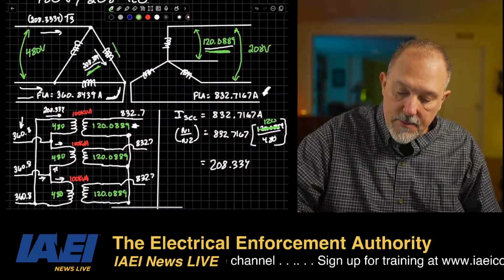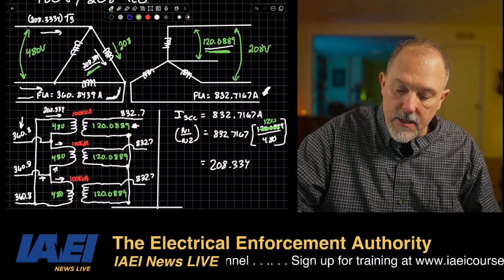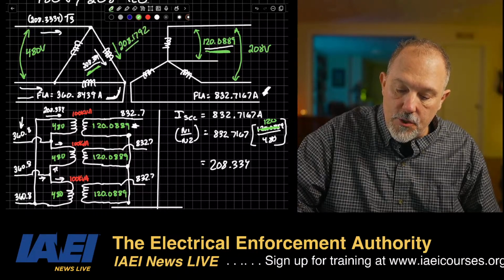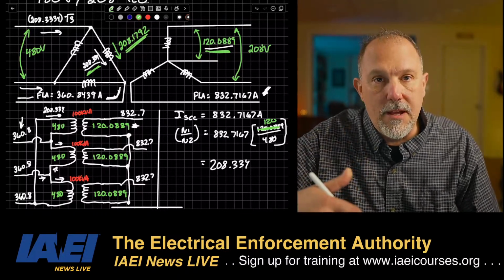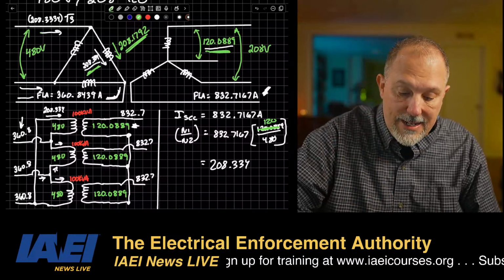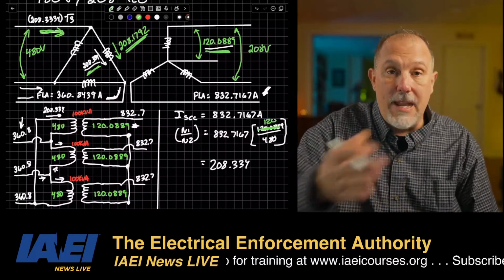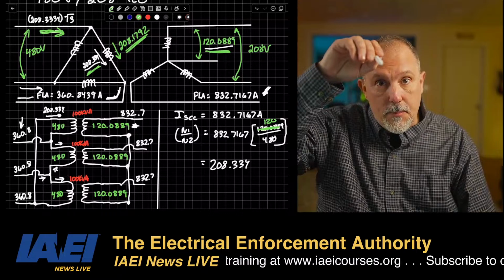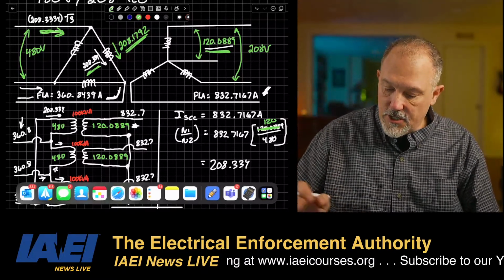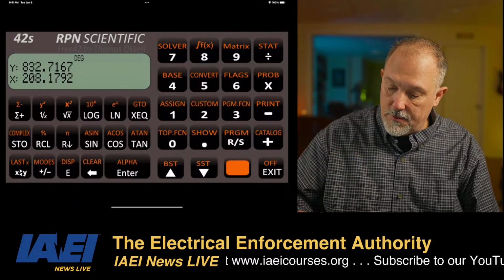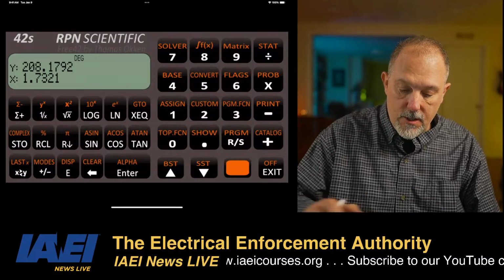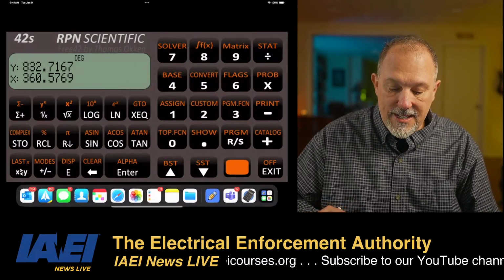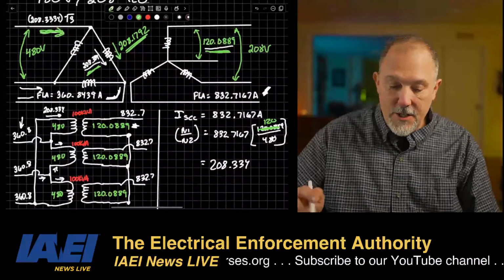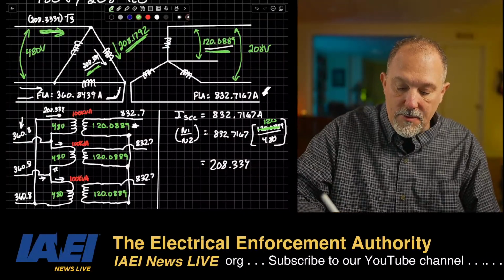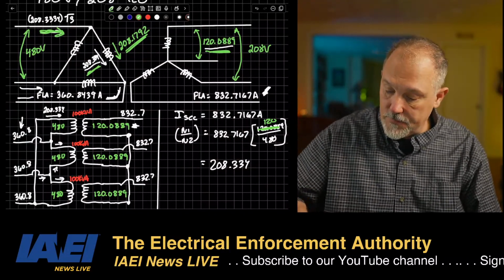So this number here becomes 208.1792. And then I have to multiply that by what? The square root of 3 to get the current on the line side, because that's just what's through the primary in a delta connected. So I've got to multiply that by the square root of 3. Square root of 3 times that gives 360.57. So now I am at 360.57.